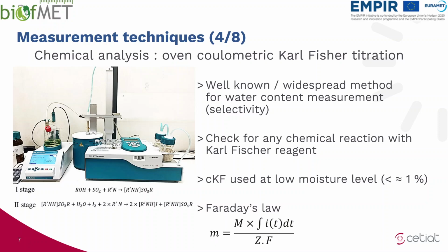Faraday's law is directly related to the coulometric Karl-Fischer titration method, as it describes the relationship between the amount of electric charge passed through an electrochemical cell and the amount of material being deposited or dissolved at the electrodes. In coulometric Karl-Fischer titration, Faraday's law is used to determine the amount of water in the sample based on the amount of electric charge passed through the cell during the titration.